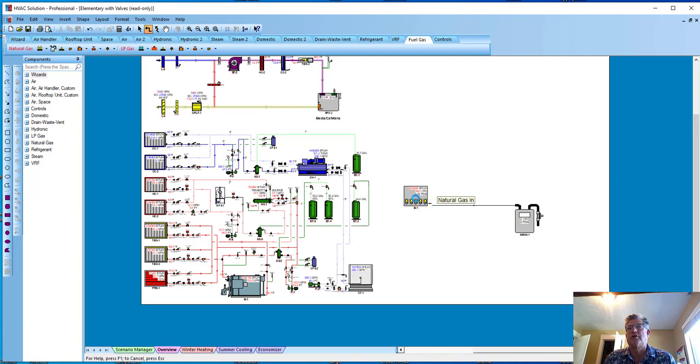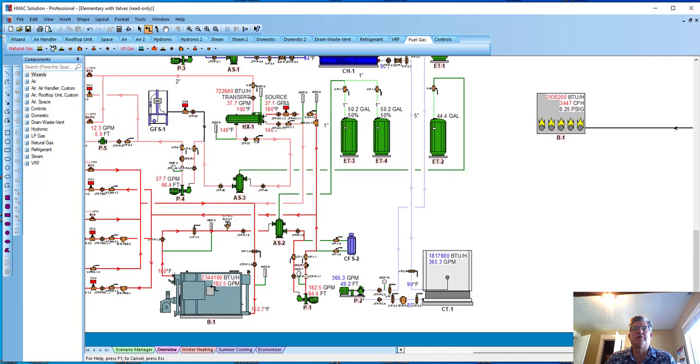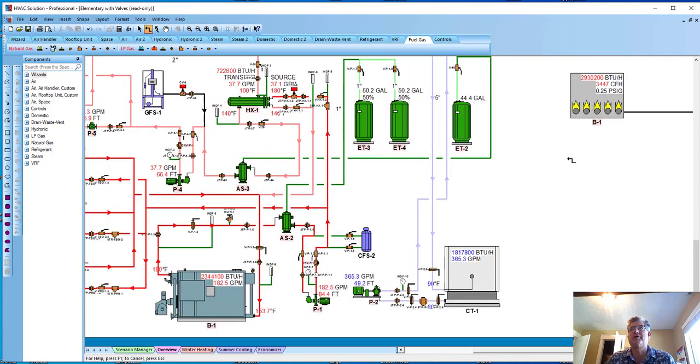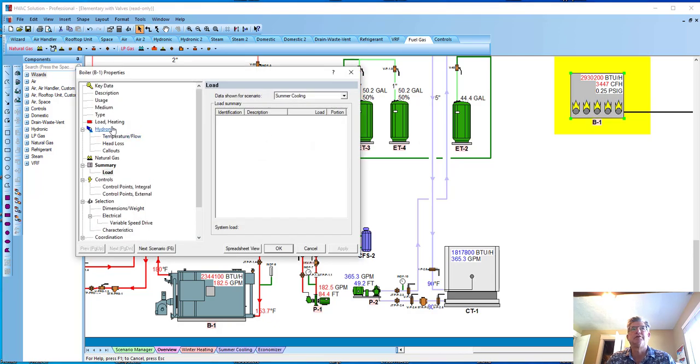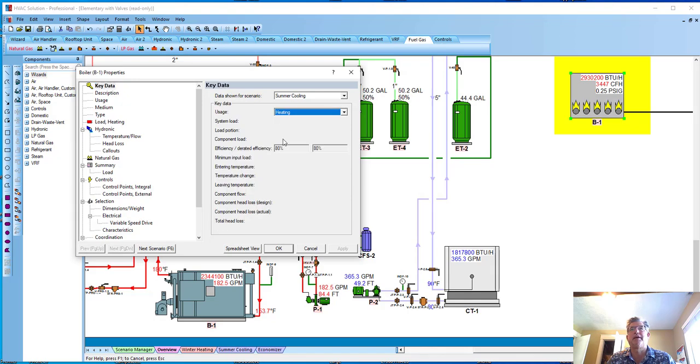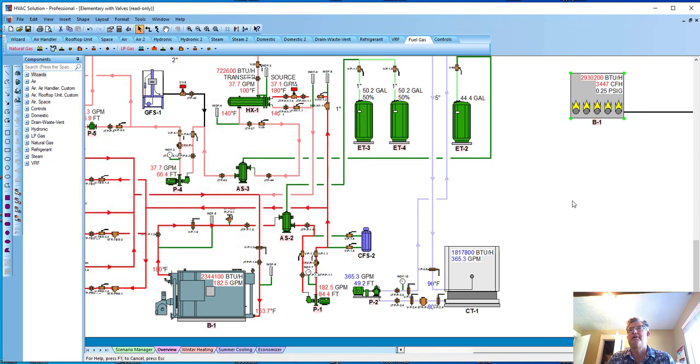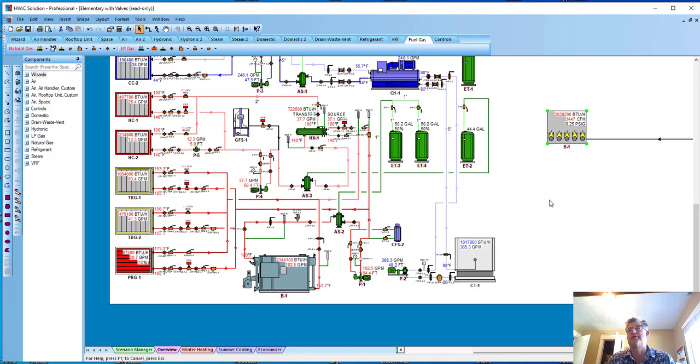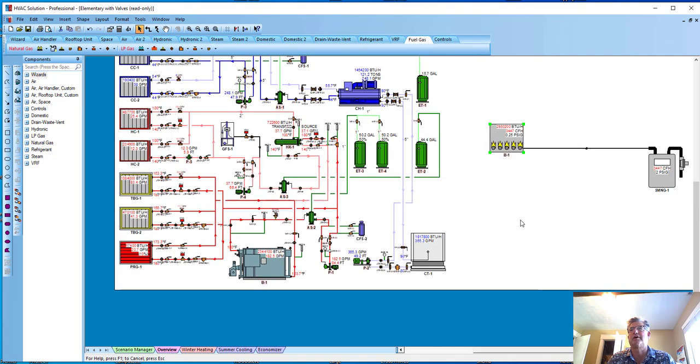You'll see the load of that boiler over here. There's so many BTUs when it gets done calculating that. You'll see the load there is, what, 2.3 million, a lot higher here, right? Because we have altitude correction and efficiencies of the boiler that are taking place, that happen derating, which you need to take into consideration when you're looking at sizing that.